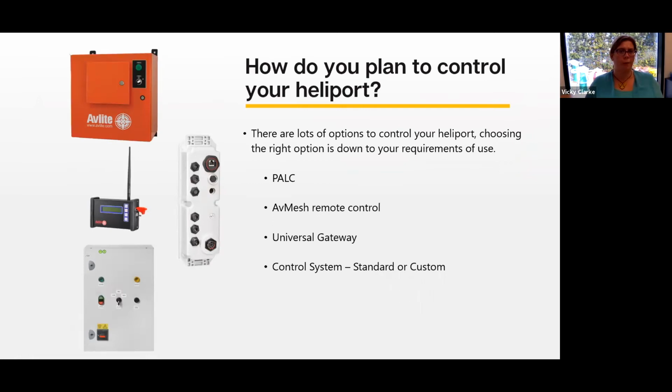With control, we have a variety of options, from a simple single push-button operation, through pilot activation, up to customizable timeouts or incorporation into a building management system. We can integrate a gateway as well, so that the helipad as a whole can be remotely monitored and controlled through our Star2M asset monitoring and control platform. We can also combine a number of different options into a single system. For example, pilot activated lighting with Star2M monitoring and control, and a control panel locally with simple on-off switch as backup.